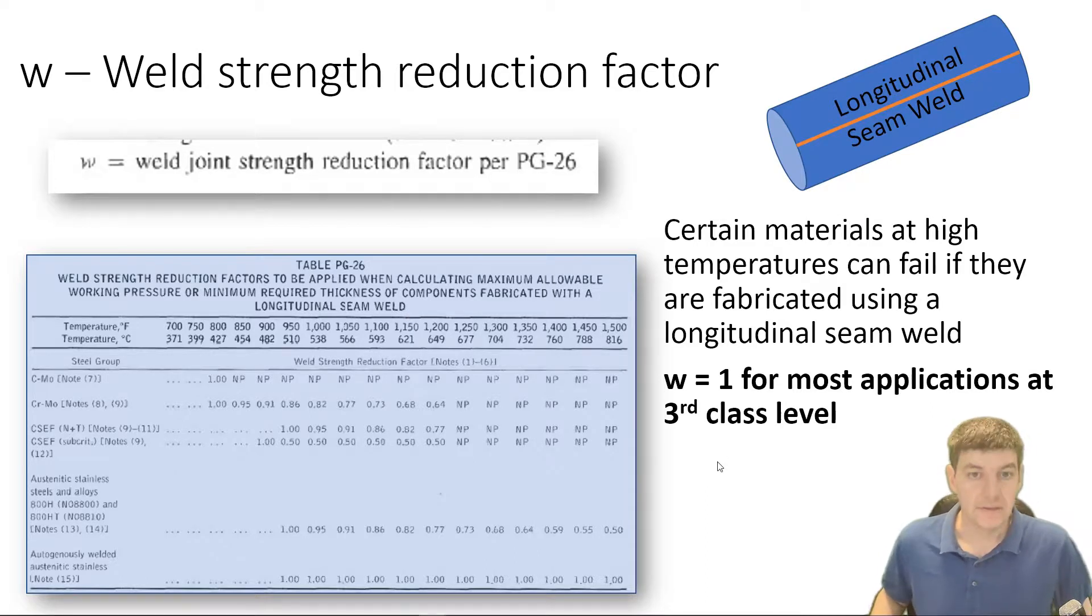And realistically, you shouldn't get a question that requires you to go to this table to find out the material weld strength reduction factor. So, I'm going to say W is going to be 1 for just about every application at your third class level. However, you still need to go and make sure that if you do have a specified material out of this table at a fairly elevated temperature, you may need to find a value for W for your application.